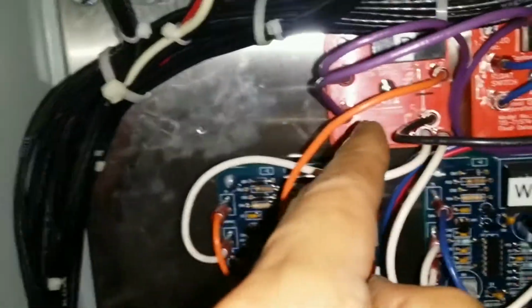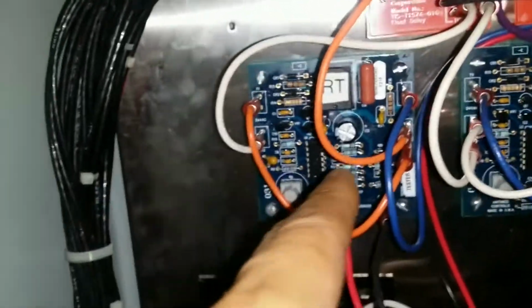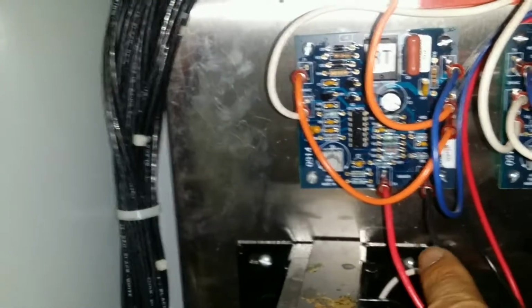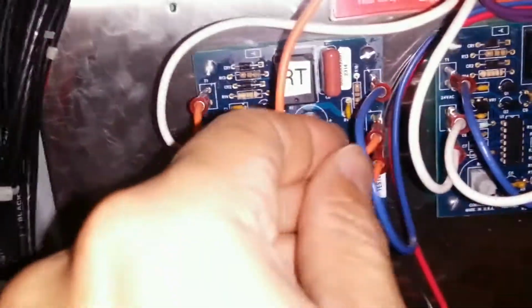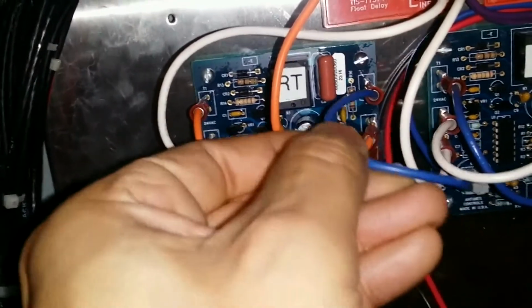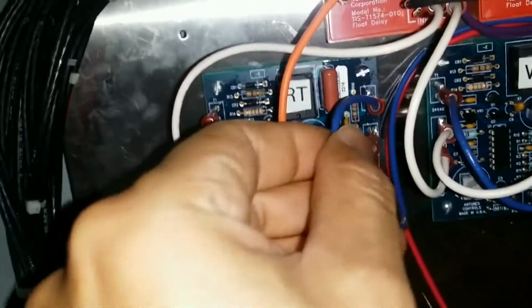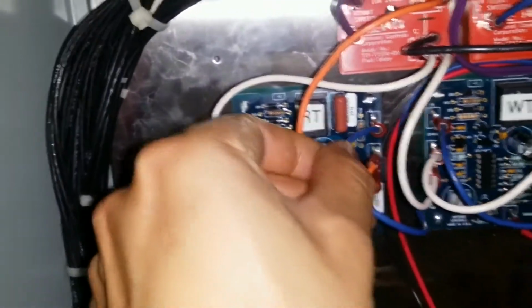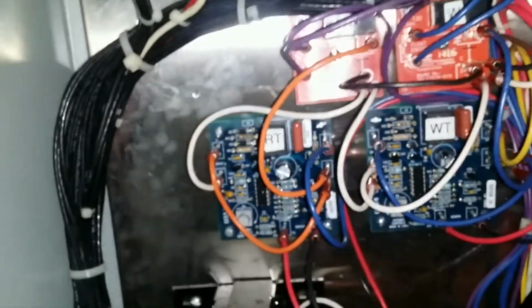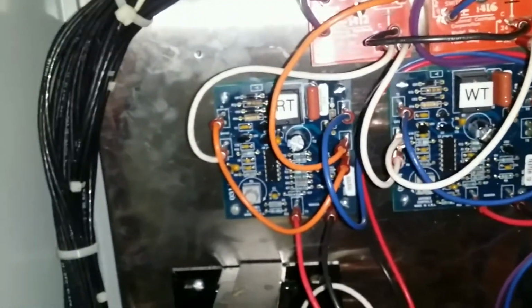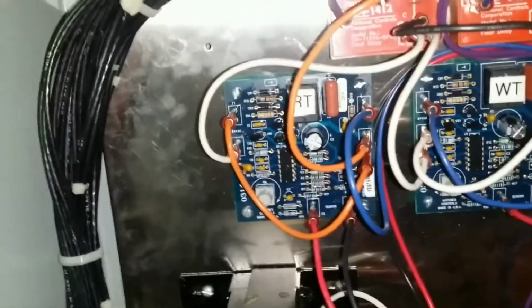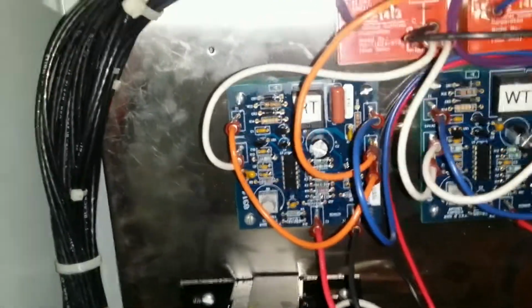And that makes sense, because we don't want this card to work whenever the tank is empty. So if this one says that there is water, it will give power to this circuit card, and this circuit card will sense via these wires the temperature of the tank, and then decide to energize the solenoid for the steam tank. If this was an electrical heater system, it will energize the contactor for the heaters. And you definitely do not want to energize heaters when there is no water in there, because they will burn out.